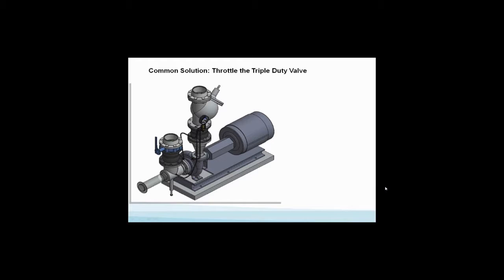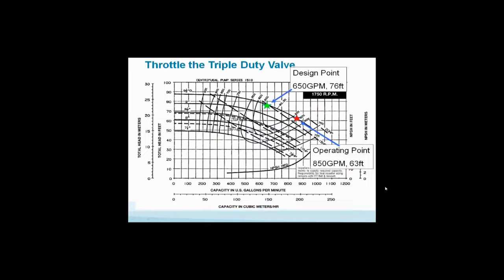So let's go back and try some simple solutions like we normally would do. The first thing a mechanical contractor would probably do here is throttle the triple duty valve back, and we can back the pump up the curve and get back to design flow. In other words, all we're going to do, and I think this picture shows it, is throttle. The little yellow chart shows you. We're running at the red star, and all we're going to do is throttle back on a triple duty valve. We're going to add head. We're going to add friction loss that's not there to force the pump back up the curve so that we're at the design point where the green star is, 650 GPM and 76 feet of head.